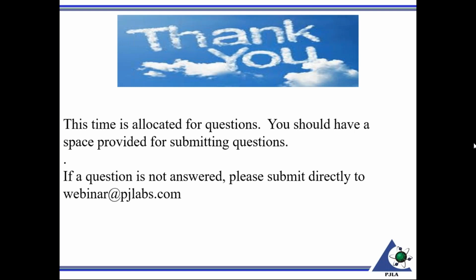You can report one blanket uncertainty on a calibration report. There is a requirement when you report uncertainty: you can always report one higher, but never lower than what's on the stated scope of accreditation. Hence, sometimes there's not a whole lot of difference between the low end and the high end, and a lab can report one blanket uncertainty just as long as it's the highest one throughout the points that were taken in the calibration.